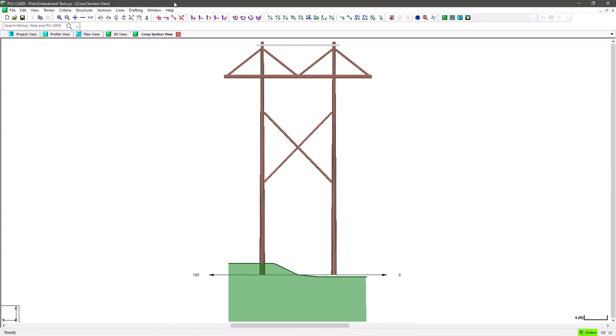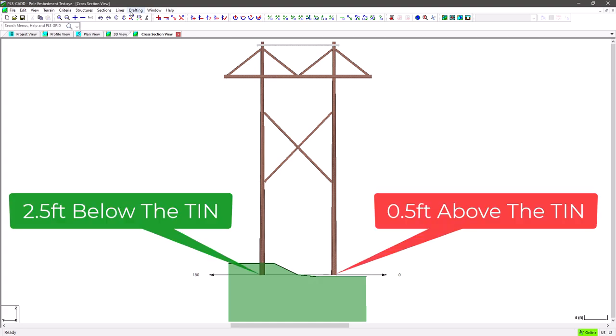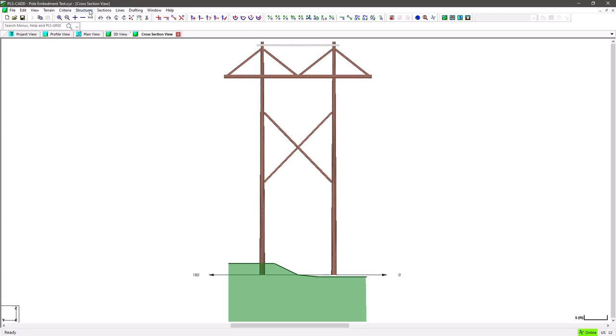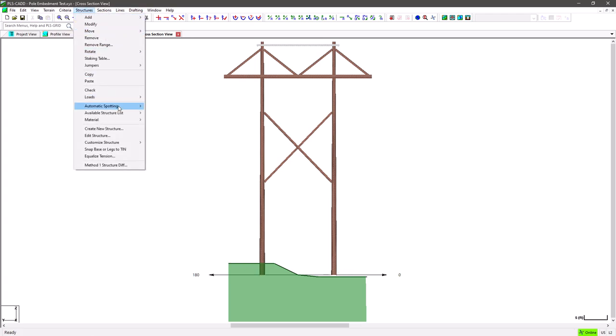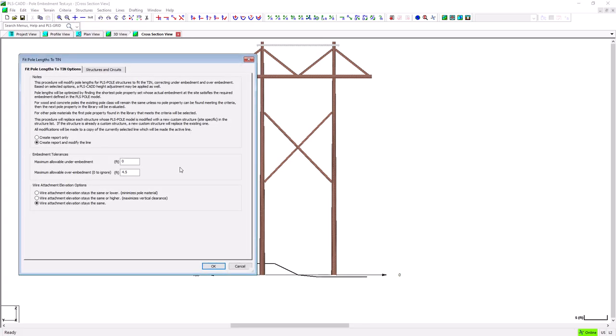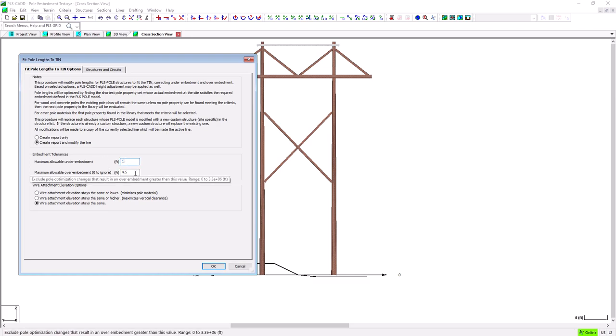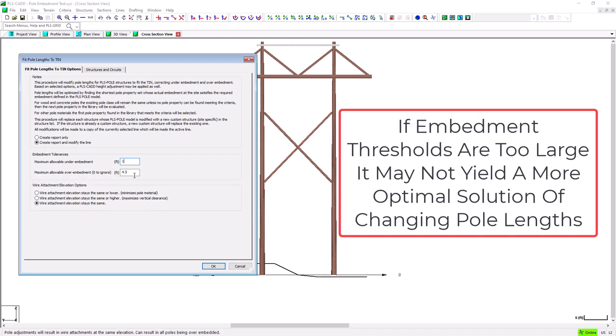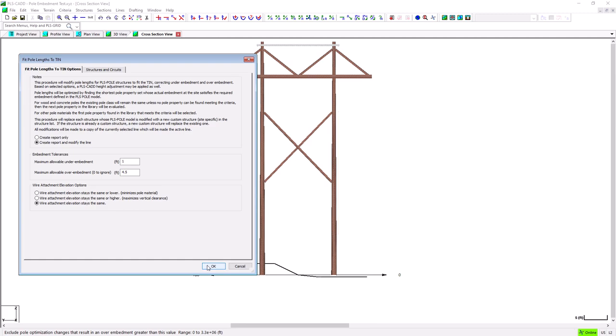Now let's quickly take a look at a few other scenarios for using this feature. So let's go back to the original model where the left pole is below the tin and the right is above it by the same distance as we previously had. This time, let's run the feature but choose the ability to specify an under embedment maximum threshold of 1 foot, and let's keep a maximum over embedment threshold of 4.5 feet. It's recommended not to go too much larger than 4 feet on either of these inputs, because if a pole needs more embedment override than that, it's probably best to simply put in a 5 foot taller or shorter pole.